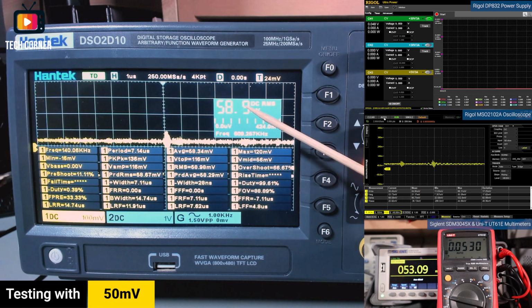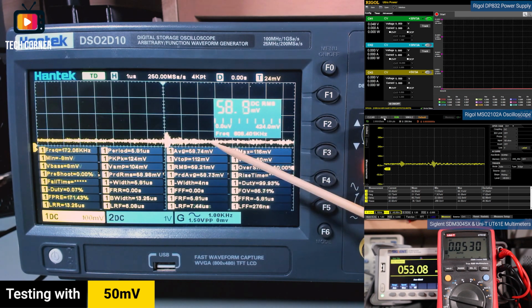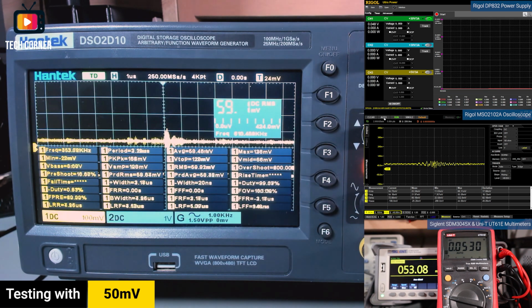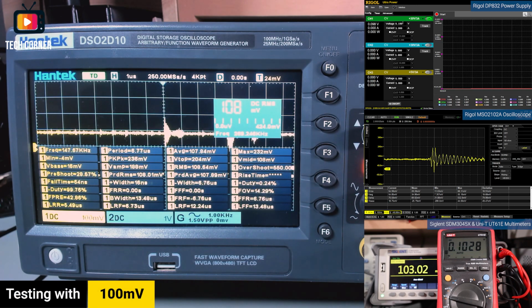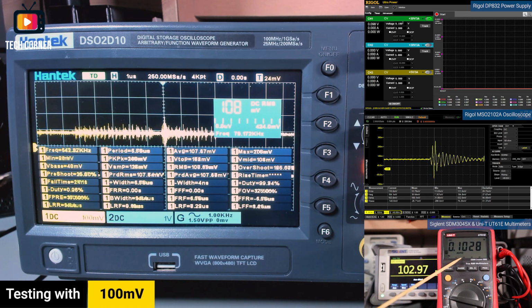This one says on the voltmeter 58, 59, average also the same, and also the same in RMS. So it has a little bit of difference, higher than the Rigol, but well, this is not a Rigol also. Okay, so let's double this to 100 millivolts. In terms of millivolts, the Rigol says 106 with an average of 103, and that's more or less the same we have on the multimeters. This one has 102, almost 3, yeah, and the same here on Siglent.